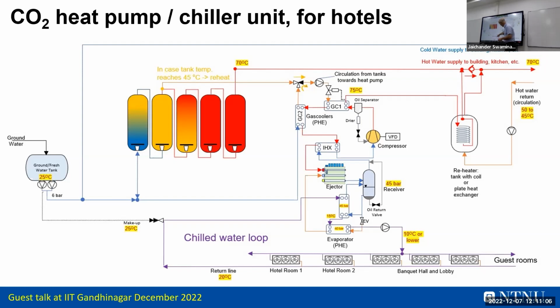Because maybe the water comes back at 15 or something. No, it's coming back more at 20. Let's say we have a staging of some of these coolers also, so it's relatively warm coming back. So we take the first cooling down to 15 in this evaporator, which is the one the compressor sees. And the second one reduces it further down to 10 by the ejector. Because our ejector is a small compressor, actually. It's driven by this gas, but it's able to suck a lot, to do a lot of pre-compression. That's what we do. So we boost the suction pressure of the compressor quite dramatically, 5, 6, 7 Kelvin.